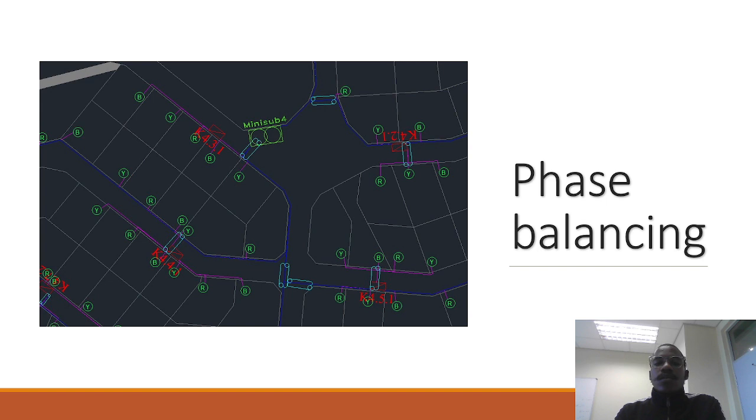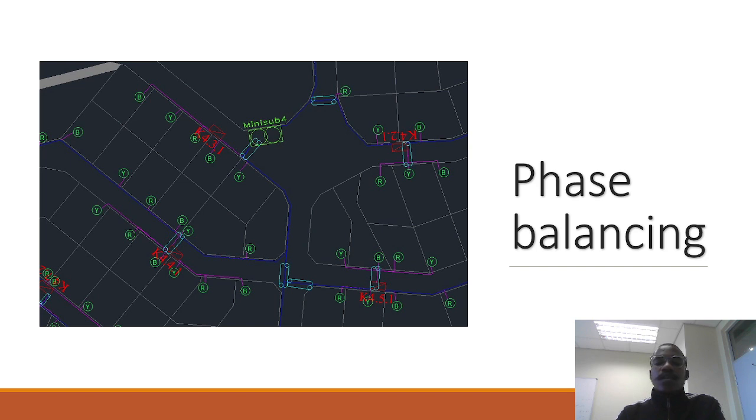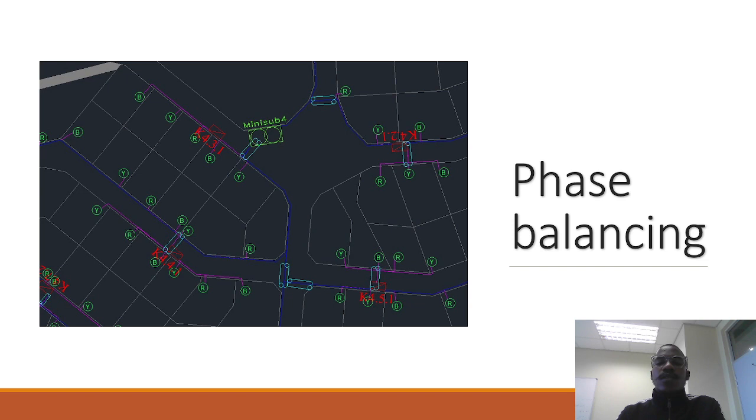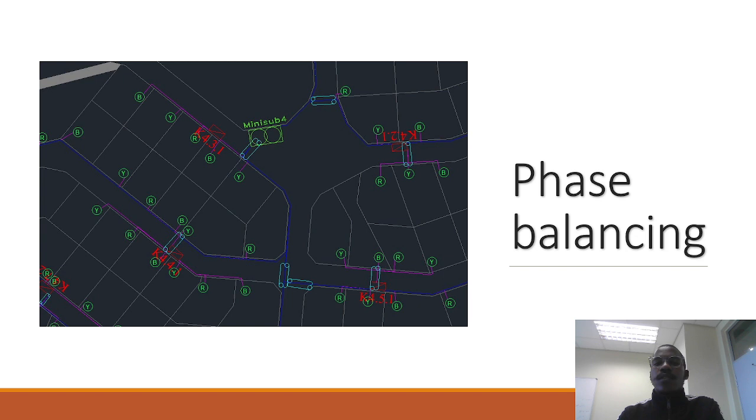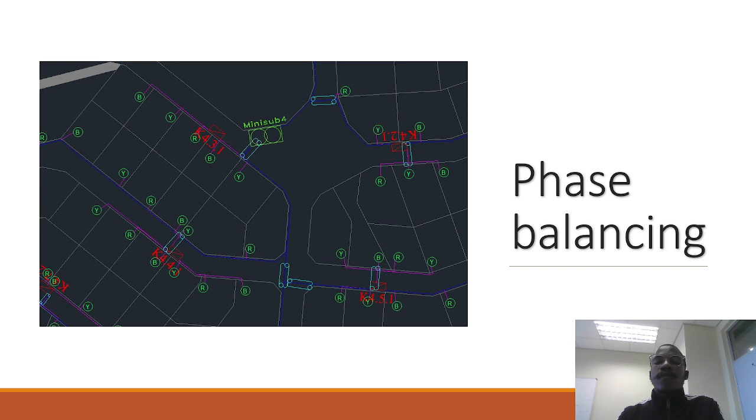We also would like to do in reticulation what's known as phase balancing. This is just the balancing from different miniature subs and kiosks, just to balance the phases: the red, yellow and blue phase. You don't want so many houses connected to the red phase or the blue phase or the yellow phase. You wouldn't want an instance whereby you have got 10 houses connected to the red phase, 5 houses connected to the blue phase and 2 houses connected to the yellow phase. You would rather have like 5-5-5 on each phase, which is red, blue, yellow respectively.